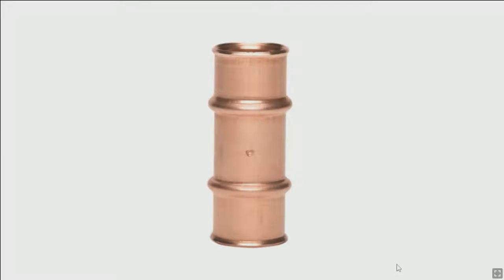These fittings, you take a quarter inch fitting, it's going to go to 6,500 PSI. So there's no water getting in there, and even if you could, it would never have the pressure to break those two circular bands. When you mechanically work harden copper, it goes from soft to hard - that's what we call a work hardened joint. You're taking an annealed piece of copper and pressing it, and that joint now is hard copper.